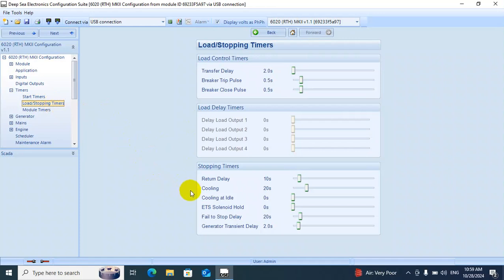Here we have cooling. When we want to stop the generator, it will run about 20 seconds to cool down. The cool down at idle is 0. When there is no load, we start the generator and we stop it, it will suddenly stop. There will be no cooling time.